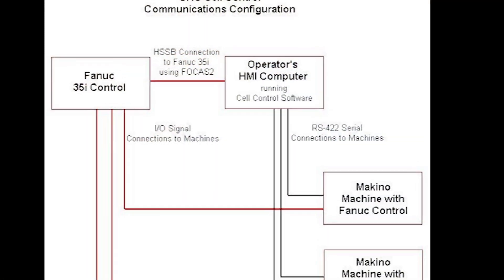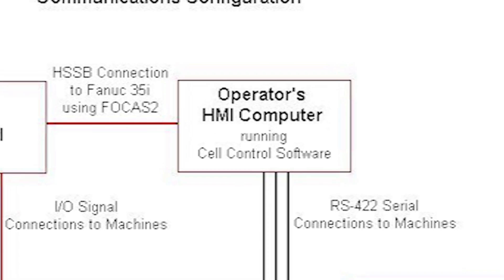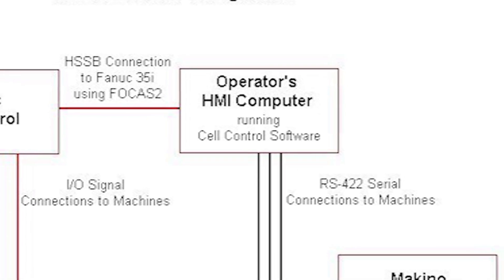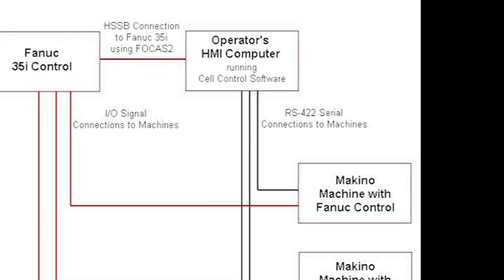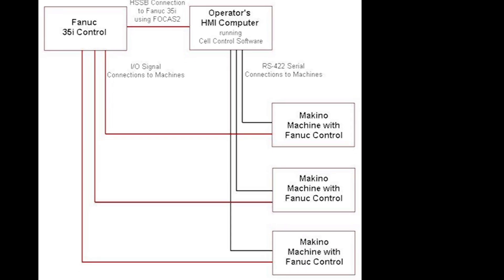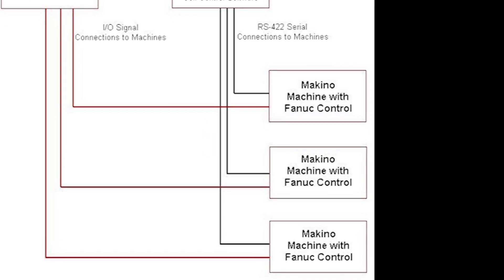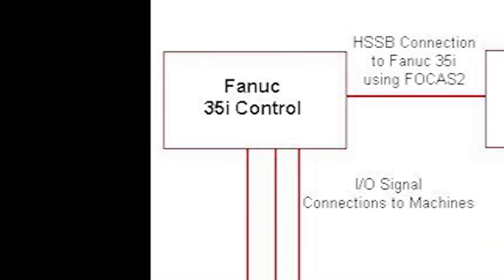Open Vision Cell Control software communicates with the FANUC CNCs on the Makino machines via RS422 serial connections, and receives requests from machines to load and unload pallets, provides information to the machines about the pallet being loaded, and receives information about the machine pallet from the machines. The FANUC 35IB motion controller also communicates with the FANUC CNCs on the Makino machines via I/O signals.